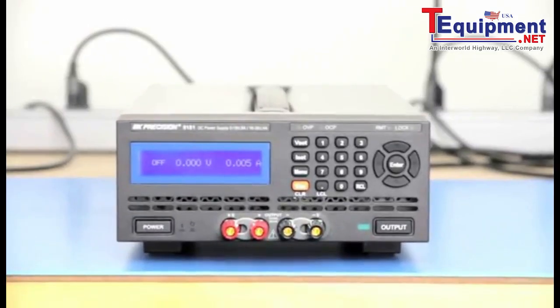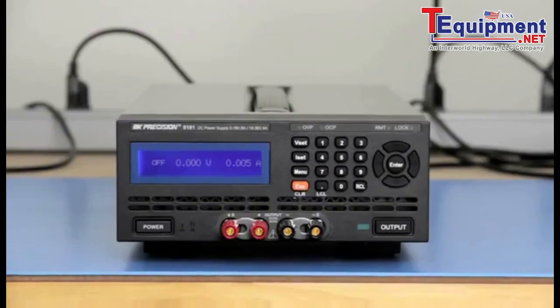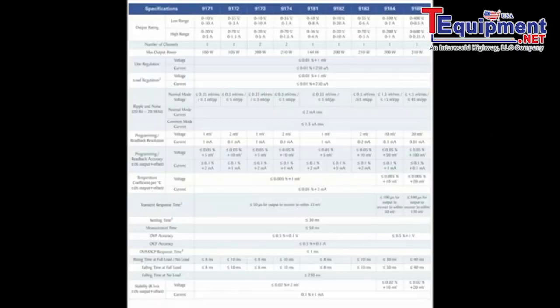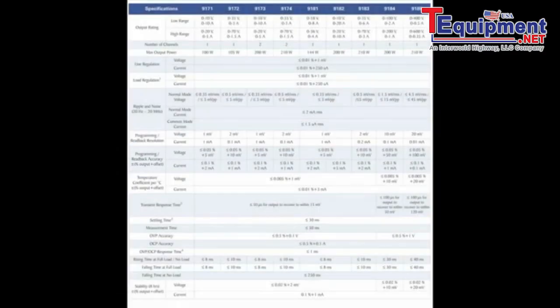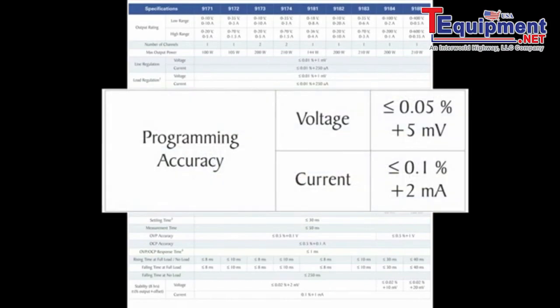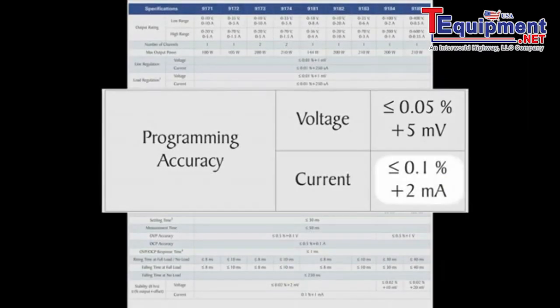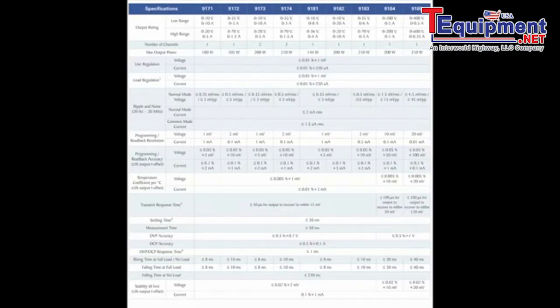In this video, we will use the 9181 programmable DC power supply as an example. This power supply specifies two different accuracies: programming and readback. Its programming accuracy is specified as less than 0.05% plus 5 mV, and less than 0.1% plus 2 mA.